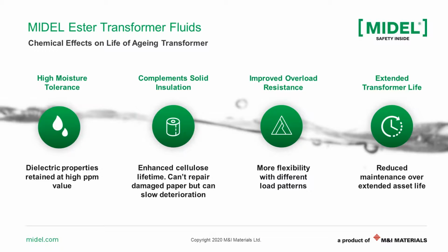At the same time, that means the cellulose or solid material will be drier if they use the ester liquid. And as we know, if the cellulose material is drier, the lifetime of the cellulose will be longer, and at the end, the lifetime of the transformer will be longer.